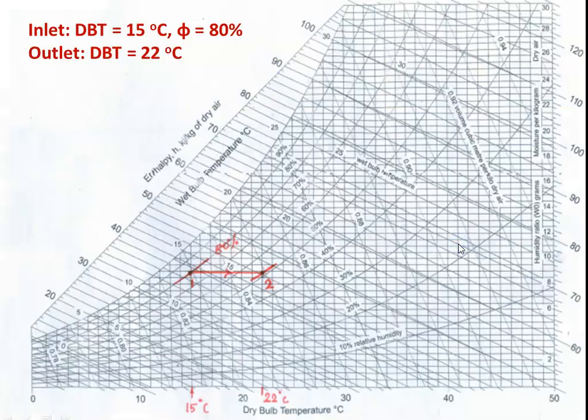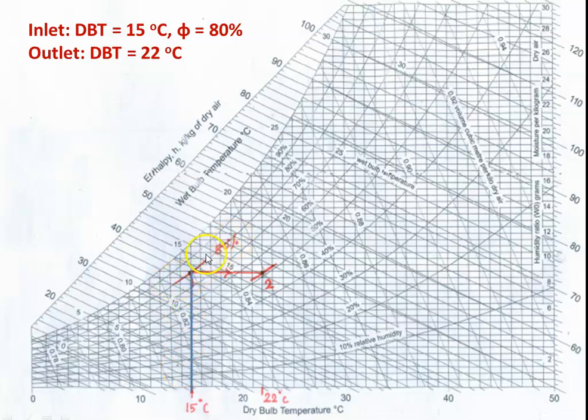This problem is solved using the psychrometric chart. The inlet condition is dry bulb temperature 15°C and relative humidity 80%. The outlet condition is dry bulb temperature 22°C. On the psychrometric chart, take the x-axis (dry bulb temperature). At 15°C, draw a vertical line to meet the 80% relative humidity curve — this is point 1. Then draw a horizontal line from point 1 to meet 22°C — that is the sensible heating process from inlet to outlet.